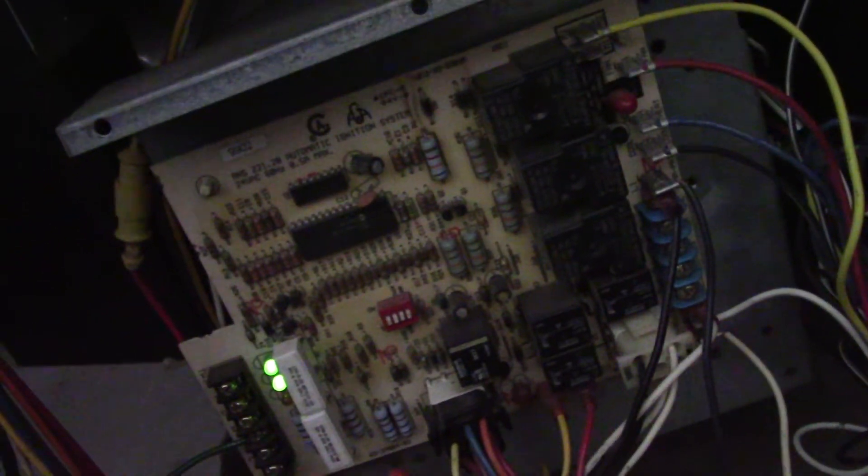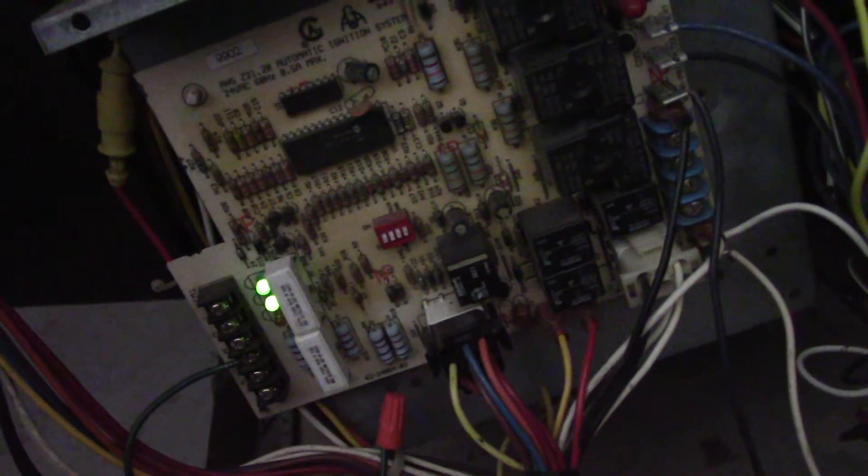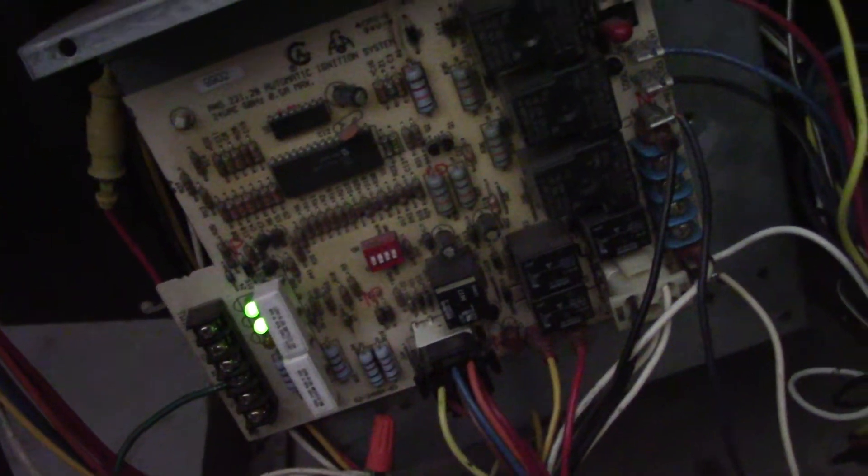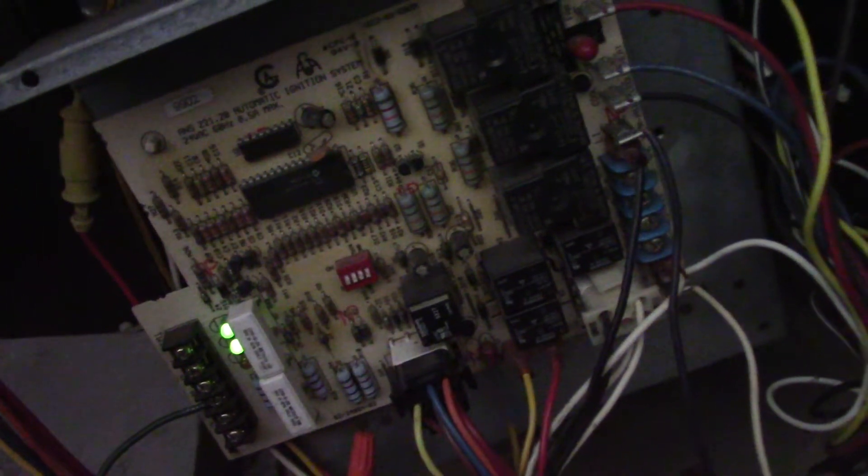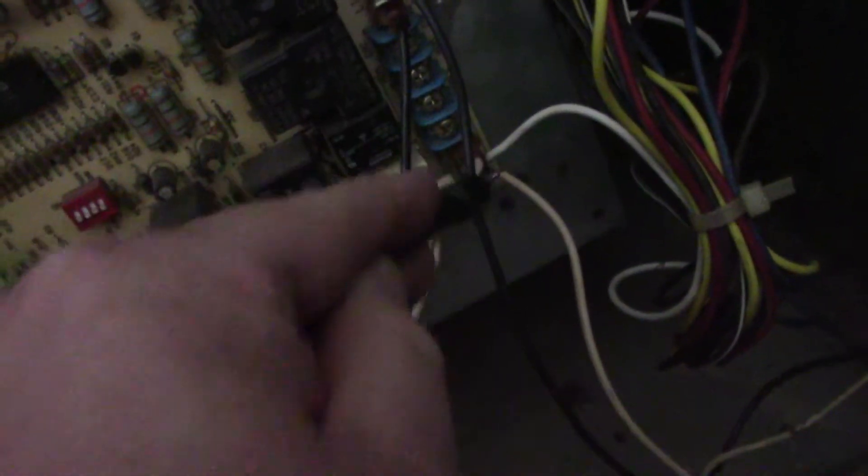Remember to disconnect power to the furnace before you mess with those high voltage lines or you're going to get lit up like the 4th of July type of thing. You can then put your meter probe here, put a meter probe there with it on to check for 120 volts out.